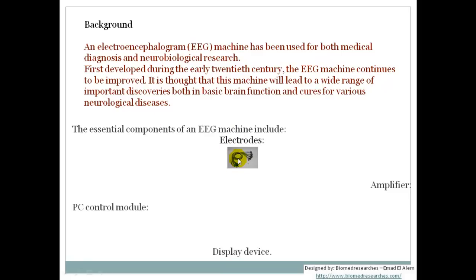The essential components of an EEG machine are: the electrodes, which pick up the signal from the scalp; the amplifier, which amplifies the signal; the PC control module; and finally the display device, where the signal is shown in a readable format for doctors to read and report.